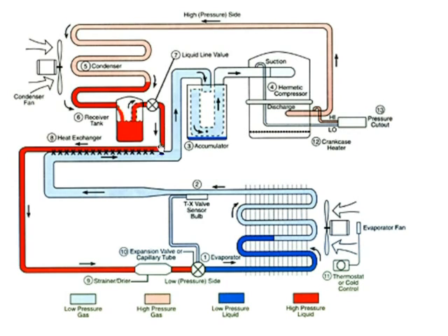Alright, and if you measure your temperature right here, and you've got a pressure temperature chart, a PT chart, you know what the pressure is anyway. So you measure your temperature and you get out your pressure temperature chart for whatever refrigerant you're working on. I mean, why do you need gauges? I don't know. Not when you're doing check and cleans. You don't need them.